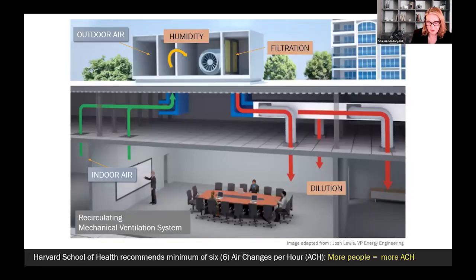Just going to review how commercial ventilation systems work. Mechanical ventilation systems circulate air through the buildings using fans and ductwork. And it's important to remember that the air is a combination of outdoor air and recirculated air. The outdoor air composition is generally from 10 to 30%, and recirculated air is 70 to 90%. So what you're really breathing is a majority recirculated air, over three quarters of it.